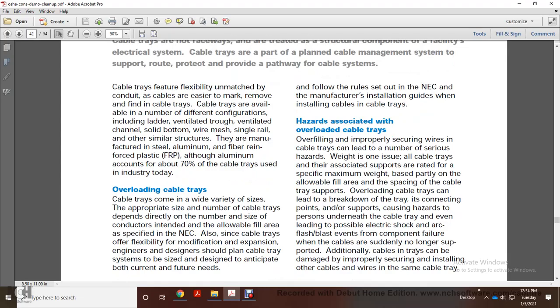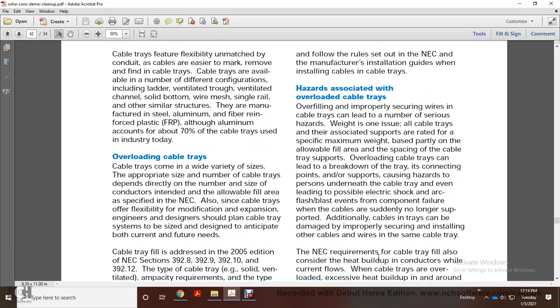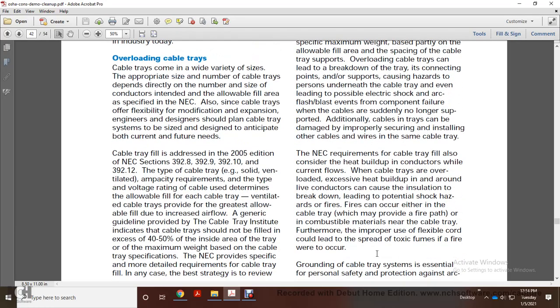Additional cables in the tray could be damaged with improper securing when installing other cabled wires in the same cable tray. National Electrical Code requirements for cable tray fill also consider the heat buildup of the conductors with the current flow. Cable trays overloaded with excess heat buildup around live conductors can cause the insulation to break down, leading to a potential shock hazard and fire.